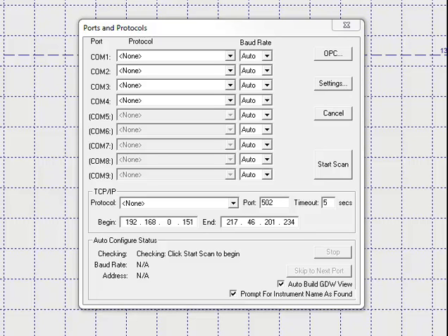In this demonstration, we have two Procon data acquisition modules connected to a serial port, COM3. We have an 8-channel thermocouple module and an 8-channel milliamp module. We're going to call them TempMon and PressMon. You want to try and compromise between a fully descriptive name and the length of the name. Long names take space on the screen and can be awkward in log reports.